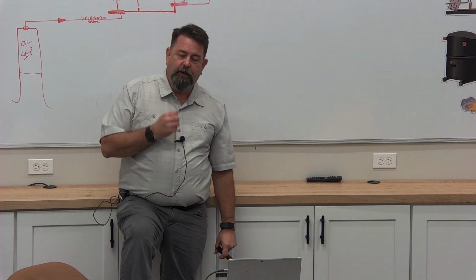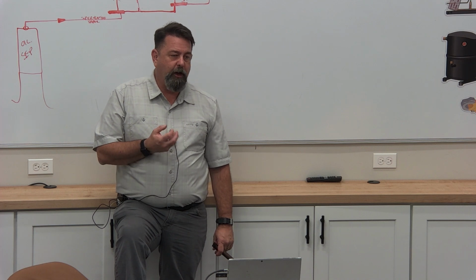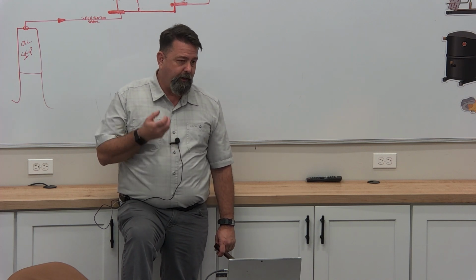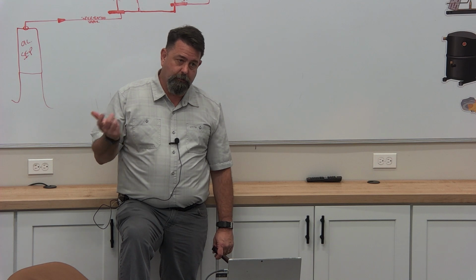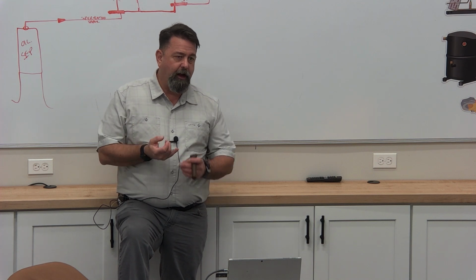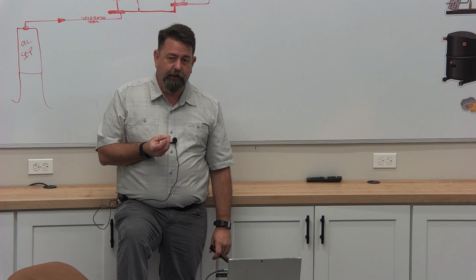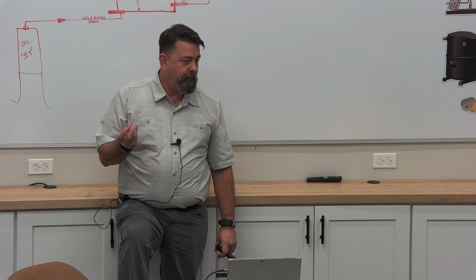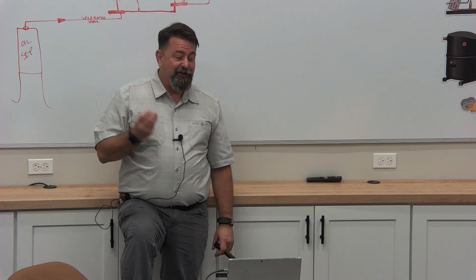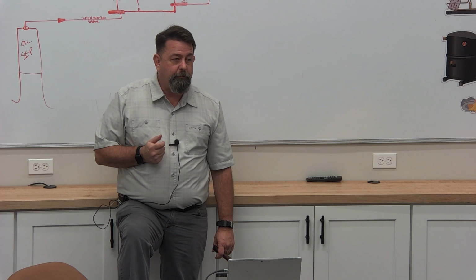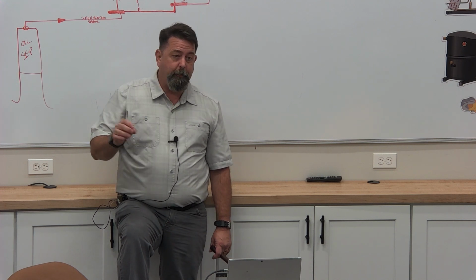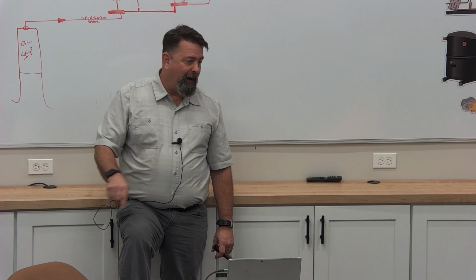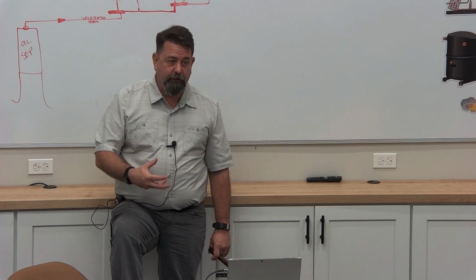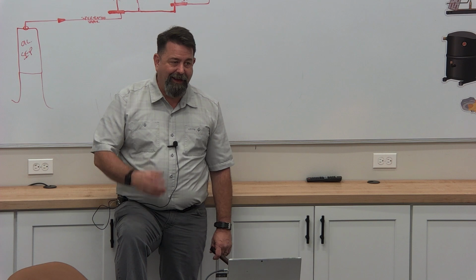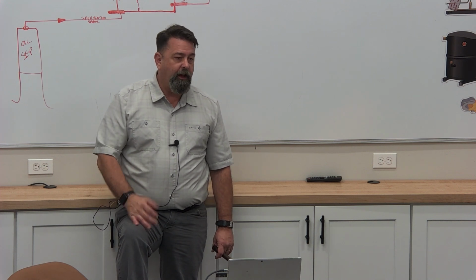Floating my discharge, there's a couple different ways to do that. The most energy efficient and the most common idea is to get subcooling out of my condenser. So to do that, I've got to measure my drop leg temperature and pressure, and I can calculate subcooling. My rack controller can do that. It's an easy program to do. Now, in order for that to work, if you remember our receiver class, I gotta be able to bypass my receiver. So that piping has to be there. I can't just convert any store that I want and keep my subcooling.